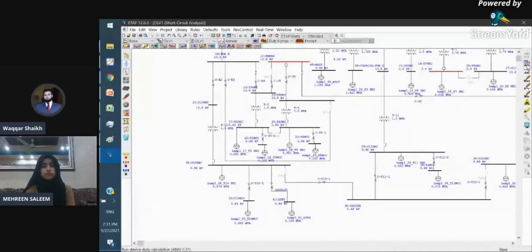The asymmetrical faults cannot be calculated just by the per unit method. For calculating asymmetrical faults, there is a technique called the Fortescue theorem, which enables us to calculate the zero sequence, positive sequence, and negative sequence. So for running the Fortescue theorem application, or for running asymmetrical faults, you should not use the first button. But mostly for equipment sizing, we run symmetrical faults and three-phase faults just by running the first option, which is called the equipment device duty.